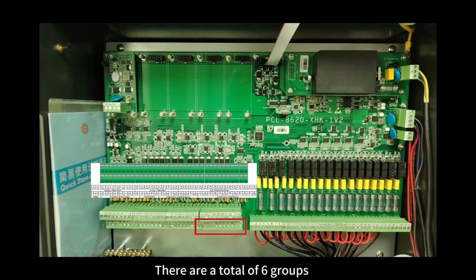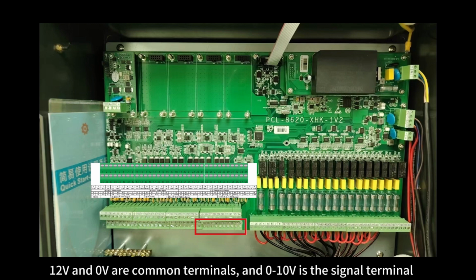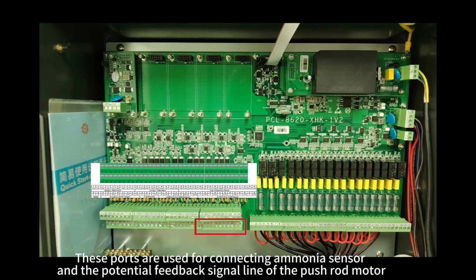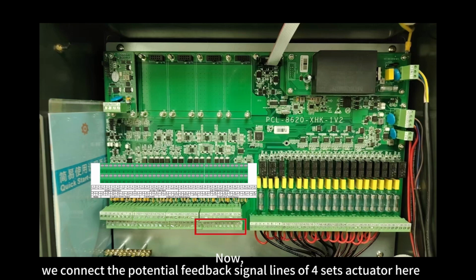There are a total of 6 groups. 12 volts and 0 volts are common terminals, and 0 to 10V is the signal terminal. These ports are used for connecting the ammonia sensor and the potential feedback signal line of the push rod motor. Now, we connect the potential feedback signal lines of 4 sets of actuators here.